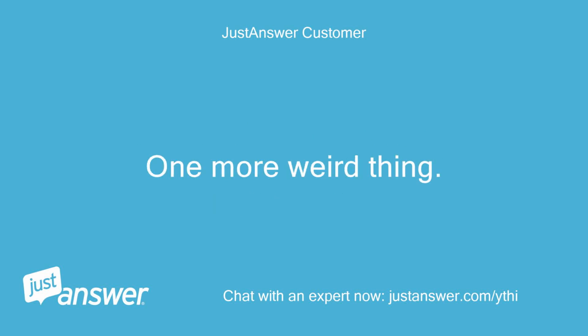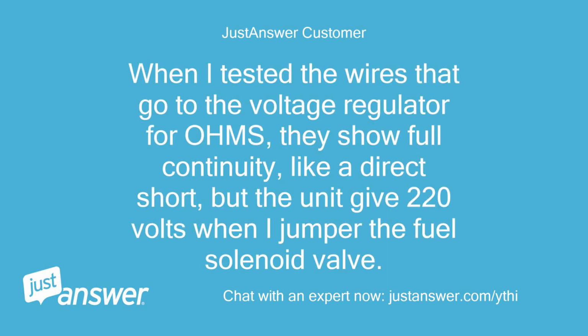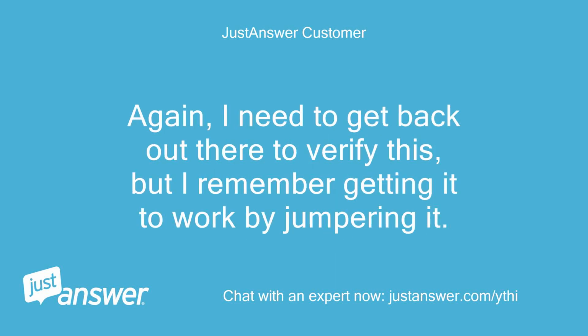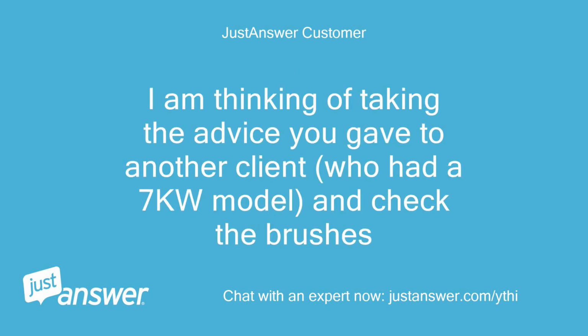One more weird thing. When I tested the wires that go to the voltage regulator for OHMS, they show full continuity, like a direct short, but the unit gives 220 volts when I jumper the fuel solenoid valve. Again, I need to get back out there to verify this, but I remember getting it to work by jumpering it. I'm thinking of taking the advice you gave to another client, who had a 7 kW model, and check the brushes.